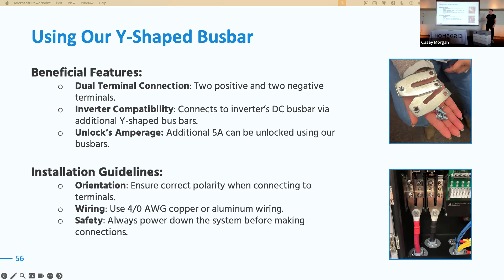So, to answer the question about how to connect multiple stacks in parallel up to the inverter: we use common bus bars, set up in a junction box between them, with one negative and one positive, and basically treat it as one giant system in parallel, connecting the batteries together via those common bus bars.